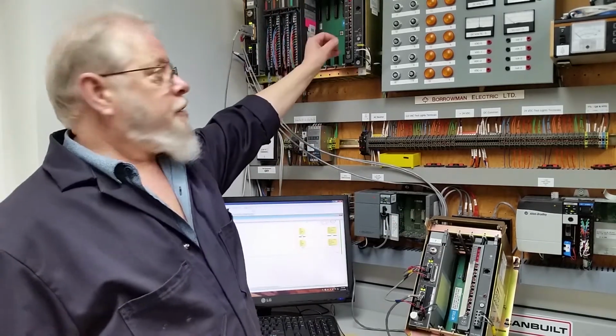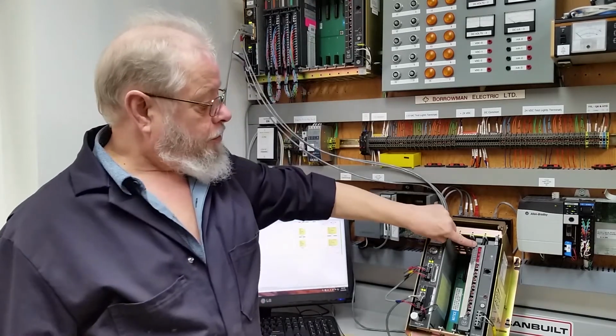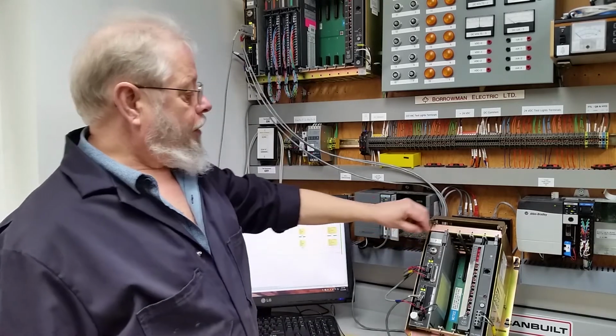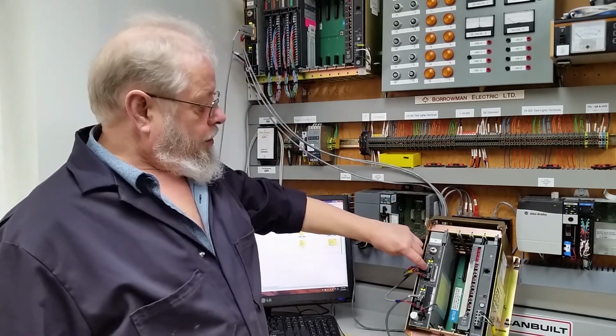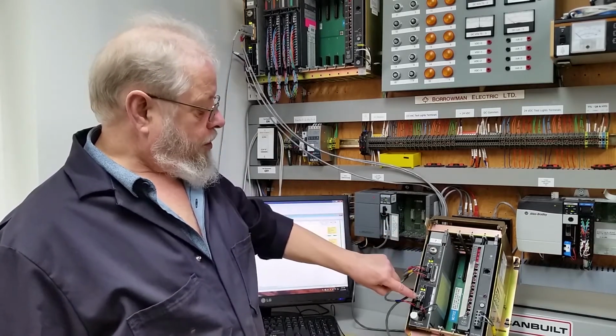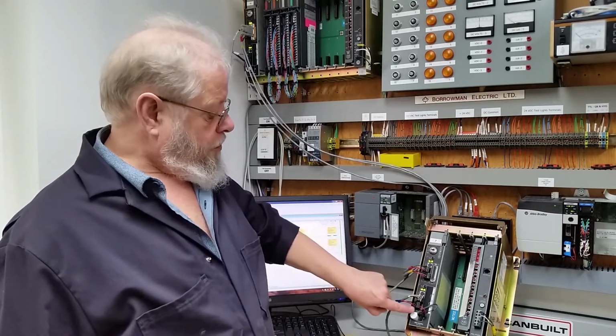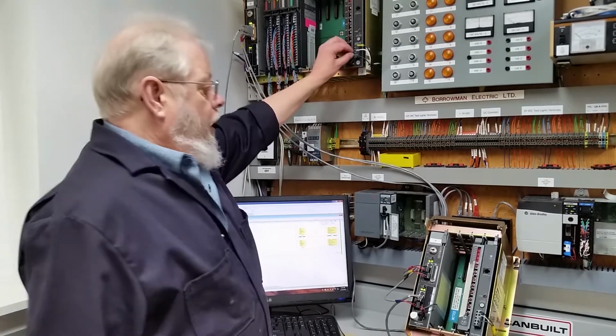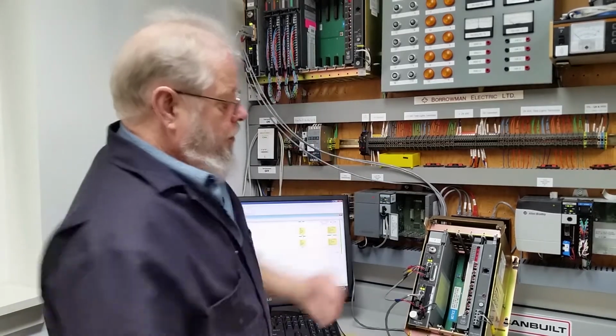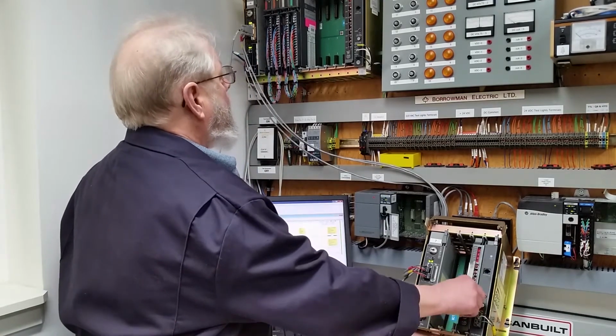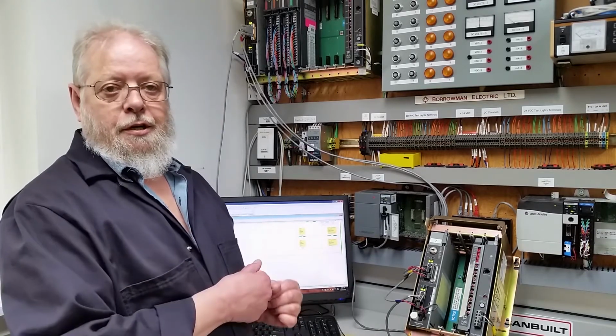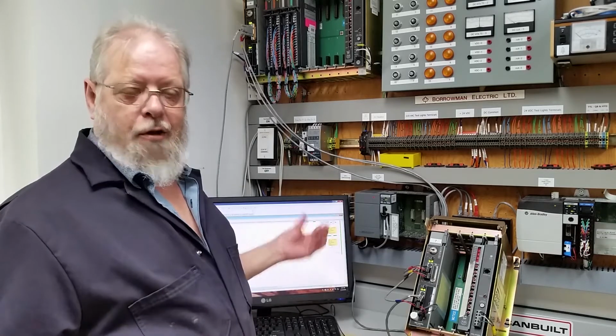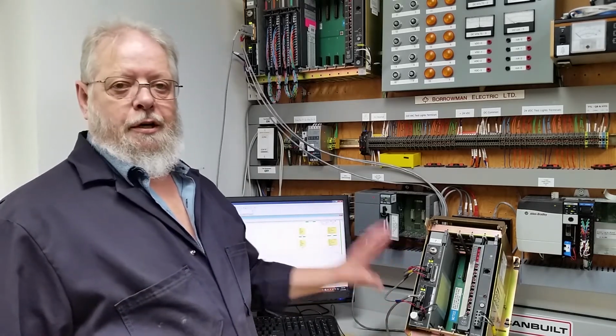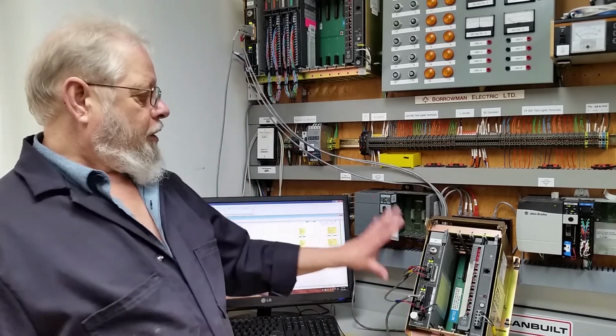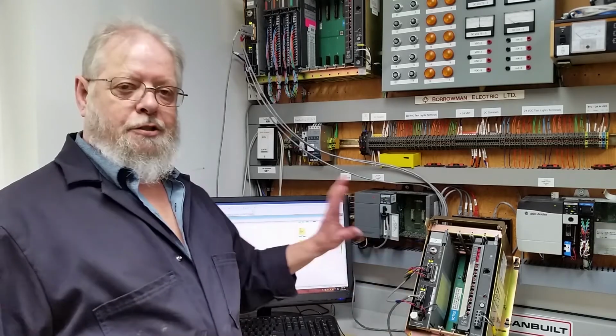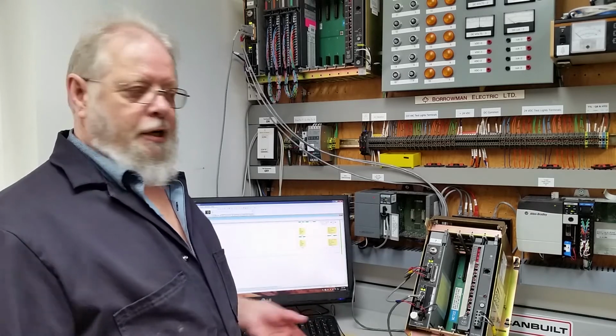So anyhow, in each chassis I've got an 8-point in and out simulation card. They're very handy test items to have. I turn the switch on here, it turns the light on here. Turn it off here, it turns it off there. The top two channels test this port. The next two test this port. The third set tests these two. And the fourth. So what this does, doing this back and forth, and back and forth, is prove that we have two-way communication. And this is just message bits going back and forth, turning on in the logic. But it proves that the ports are good. And that way you know 100% that this processor you have sitting on your shelf has been tested and is good. Put a label on it, say it's tested, when it was tested, and you're ready to go.